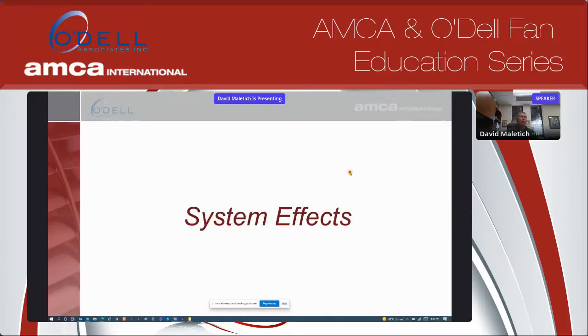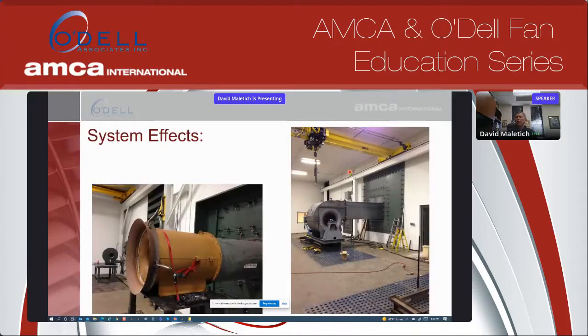Okay, moving on. So sometimes fans do not perform as cataloged. What causes that? Well, we have to look at how a fan is actually getting tested. This is a centrifugal fan, this is an axial fan or an inline fan. Notice that both of them have bell mouth inlets, which allows for uniformly loading the wheel, top, bottom, side to side, and eliminates entry losses into the fan. And in both cases, we have a straight run of ductwork to allow for that velocity profile to even out before it enters the bulkhead.